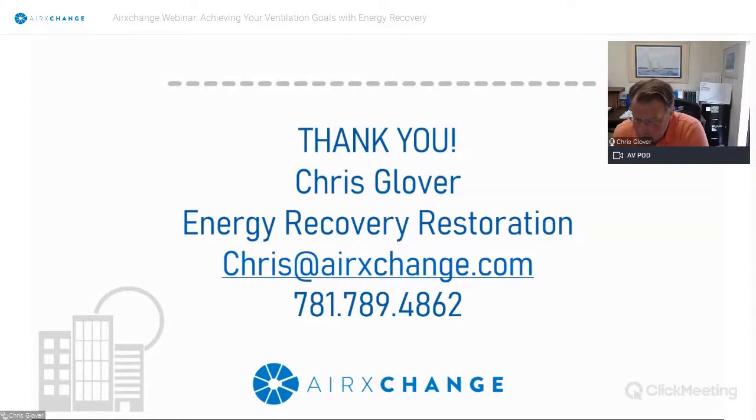We get a lot of requests to design heating and cooling loads for wheel failure, which negate the benefits of being able to reduce the design loads. I will cite your extremely low failure rate to try to sway customers in the future. That's based upon Airxchange failure rates with our 5-year warranty period. But I personally work in this environment with end users who have these devices installed, and I can say that there's a difference between perception and reality. I think the perception is that these devices will break more than they actually do.